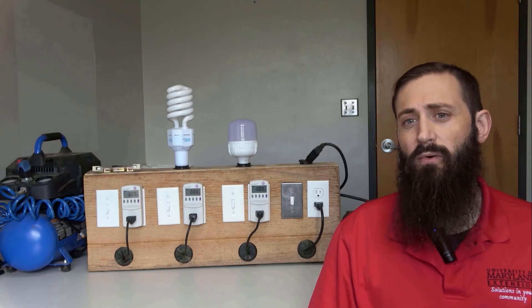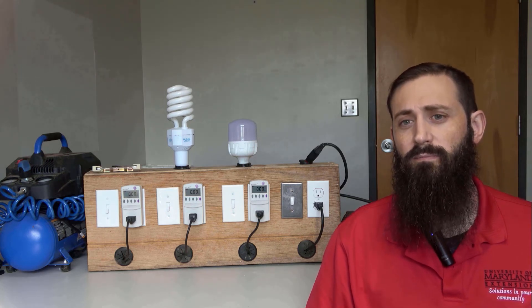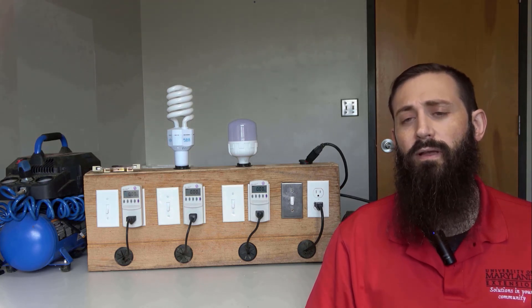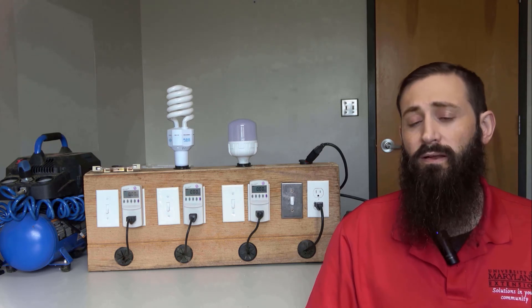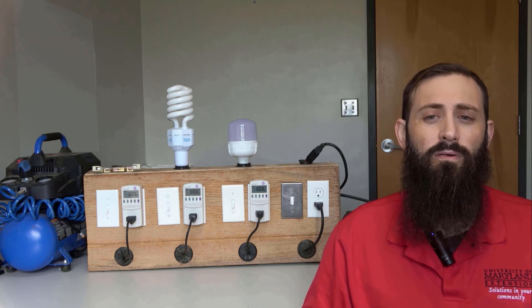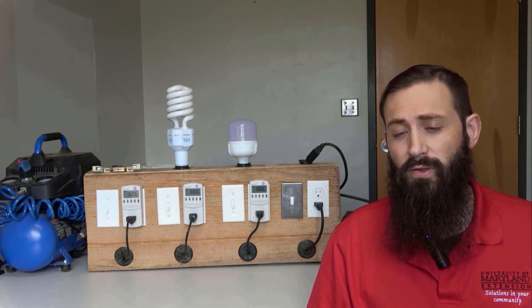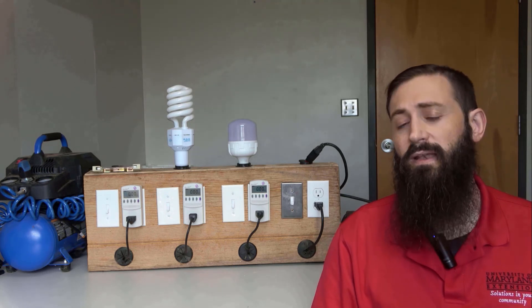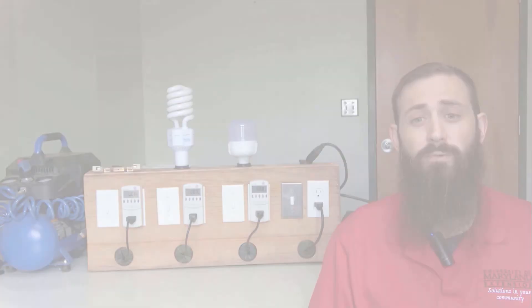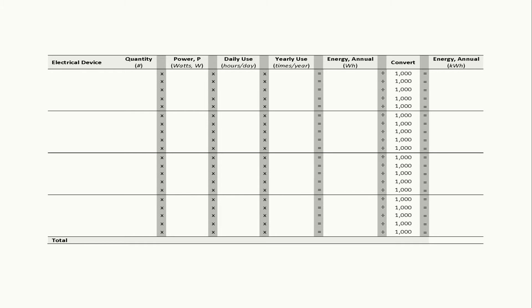We still need to address how these power measurements and ratings help in sizing a solar electric system. To do so, we'll consider calculations using either an inventory of all electrical loads or an electric utility bill. If you're considering a solar electric system for specific appliances or equipment, you may want to develop an inventory of electrical loads. You can download a simple template or calculator on our webpage at the link in the description below, or develop your own worksheet. We'll enter each electrical appliance we want to power with the solar system. As a first example, consider the small motor we looked at previously — its power was 1,150 watts when running — and assume we operate it for about 15 minutes each day, which is one quarter of an hour.